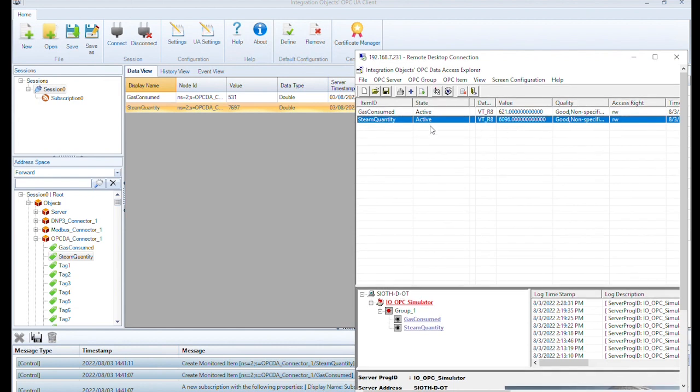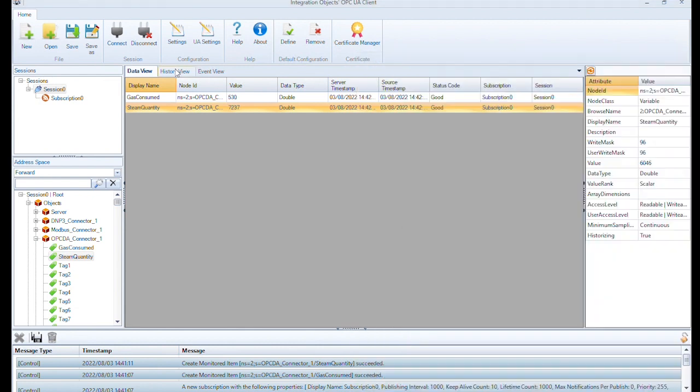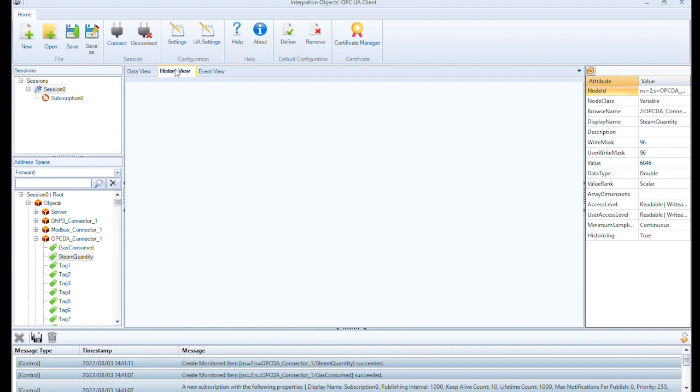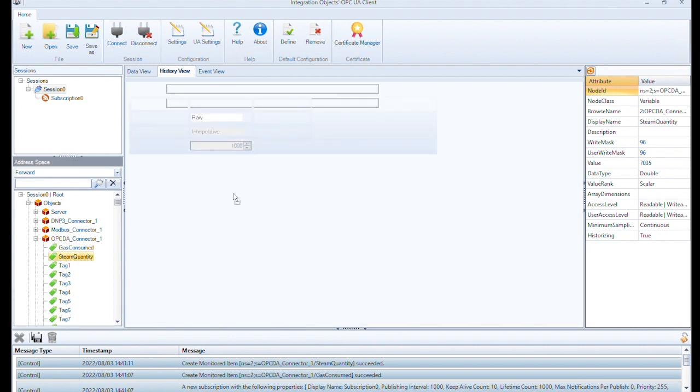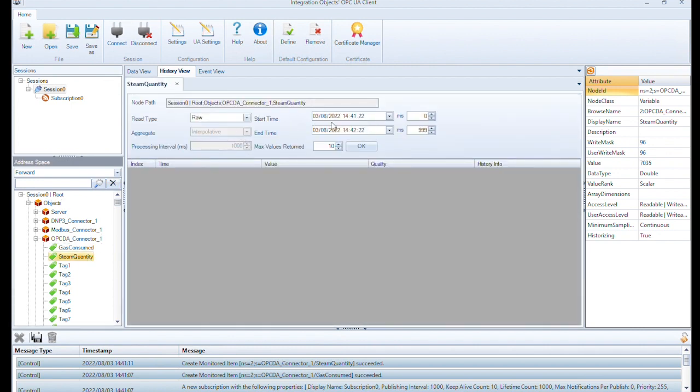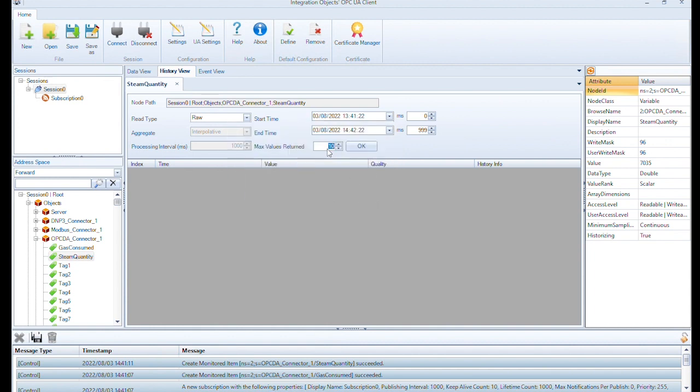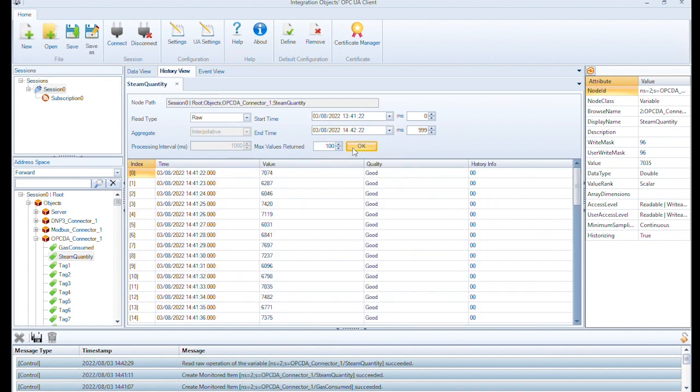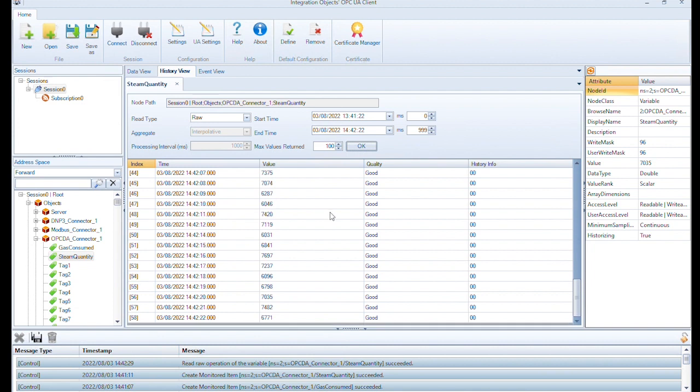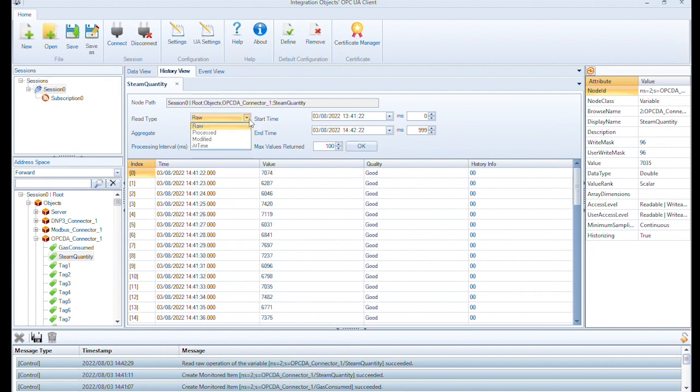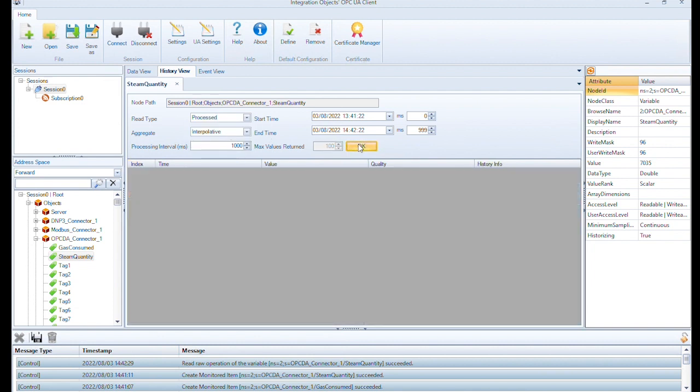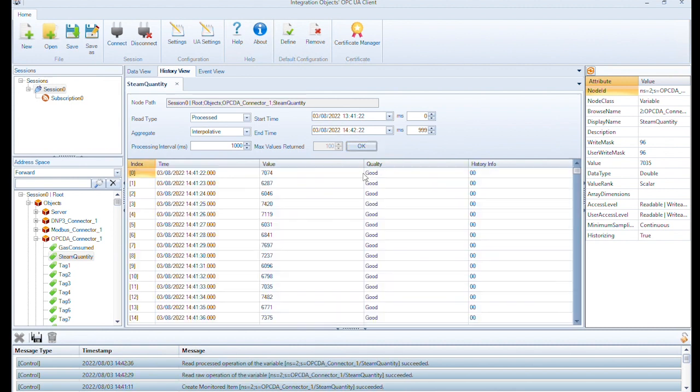We move to the history view. We select one tag from the tags for which we enabled the historical option, for example steam quantity. Select raw, specify the start and the end times. Then, click OK. We can view the historical values for the selected tag and during the selected period. Similarly, we can also view processed data from the SIOT OPC UA server.